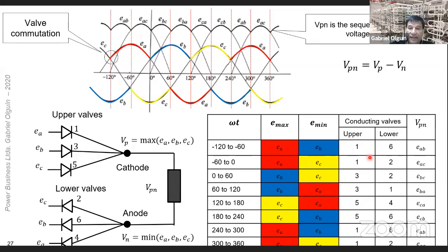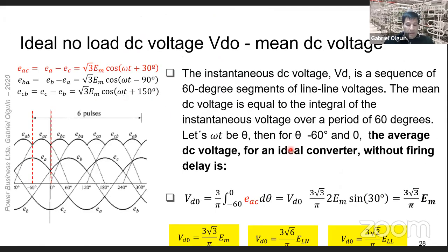Hence, the conducting valves are now valve 1 and valve 2, and the converter terminal voltage is EAC, and so on. You can review the complete table. Then the converted DC voltage VPN is a sequence of phase-to-phase voltage segments. The instantaneous DC voltage, VD, at the converter terminal between the cathode of the upper valves and the anode of the lower valve is a sequence of 60-degree segments of line-to-line voltages.